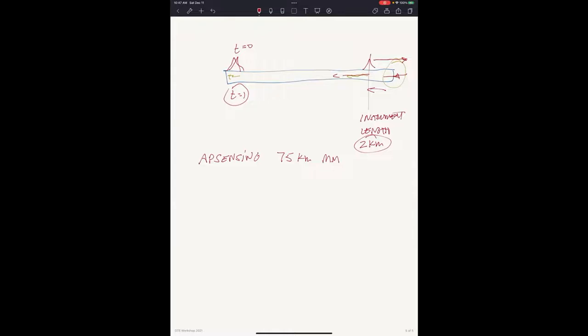When setting up your DTS, think about how long you want to average in time. The Silixa Ultima machines can report a temperature reading every second — that's 50,000 pulses averaged. Or you can average over a minute: 60 seconds times 50,000 gives 3 million pulses, which gives a much lower noise level. So repeatability is much better with longer averaging.